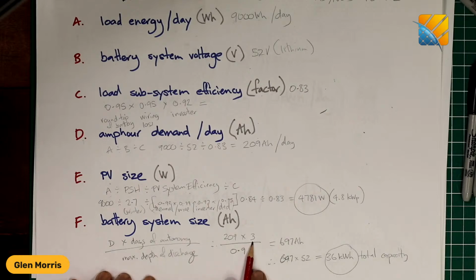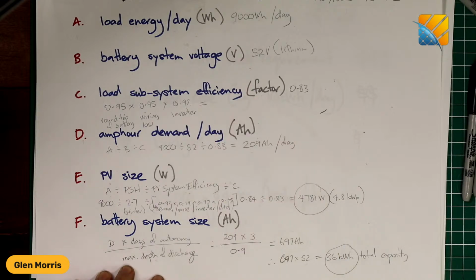I've chosen 3 here, and then I need to allow for the fact that all of my battery can't necessarily be used. Many batteries rate their capacity in total capacity, and then say the maximum depth of discharge is 80%. In this case, it's 90% maximum depth of discharge, so I can use nearly all of my battery. I've got 209 amp hours per day demand times 3 days of autonomy divided by the maximum depth of discharge, which tells me that I need a battery system of 697 amp hours. Now, if you want to convert that to kilowatt hours, you just multiply it by your battery system voltage, which was 52. So I need 36 kilowatt hours of total battery capacity to be able to deliver 9 kilowatt hours per day for 3 days during a total eclipse.